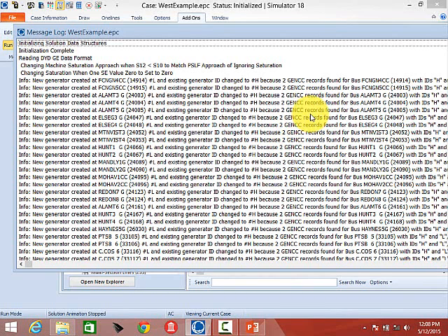In transient stability, oftentimes they're modeled as two generators. So we loaded a PowerFlow model that, in this case, would be at bus 14914. If you look at that case right when you load the PowerFlow model, there's just one generator model there. But in the dynamics data, there are going to be two actual models for generators there.